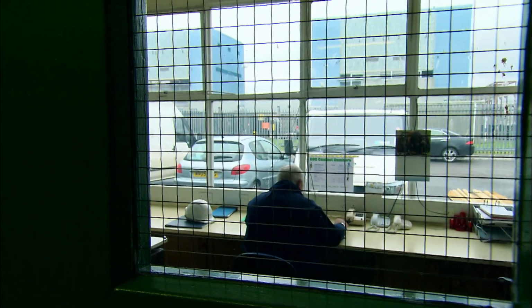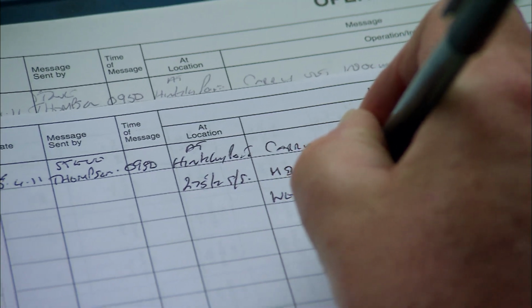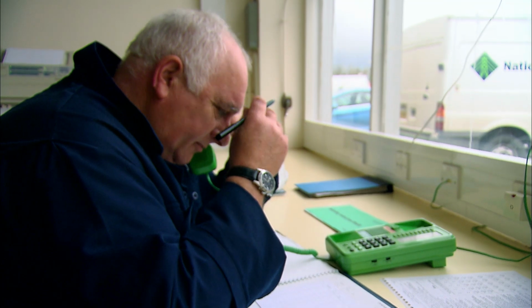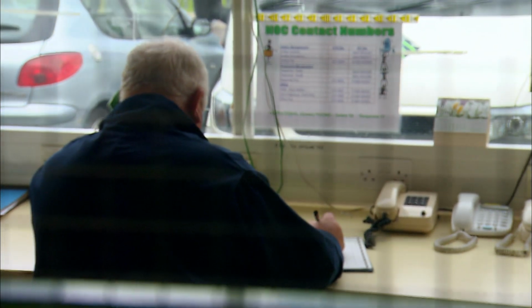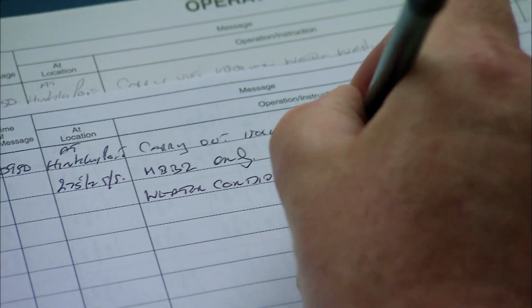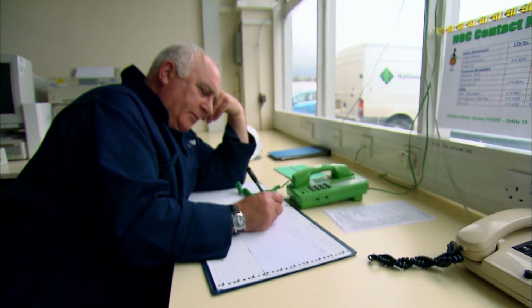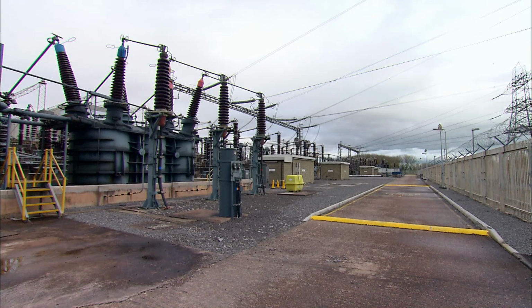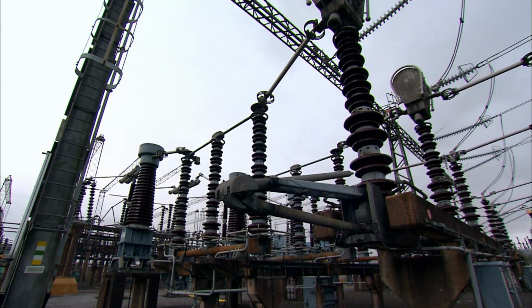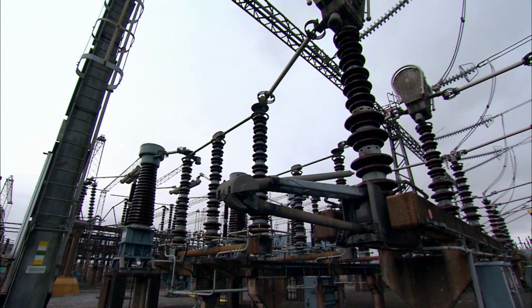Because this is a genuinely risky operation, it's vital all parties at Hinkley Point agree that it's safe to proceed. Frank needs to get formal permission to proceed with the wash. Well, that's giving us permission now to wash. So it's under our control now. Washing a live substation can cause a dreaded flashover, so they try to reduce the risk.